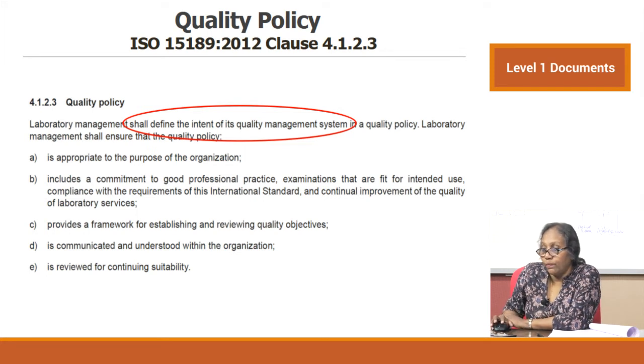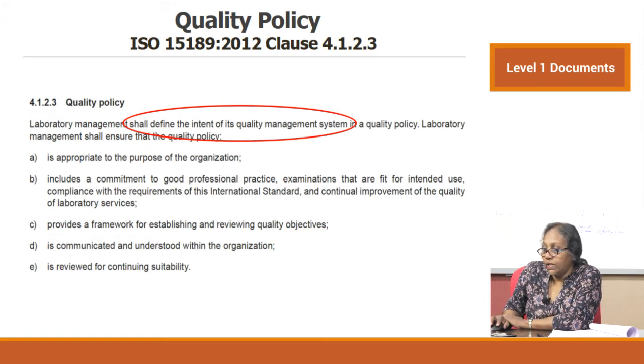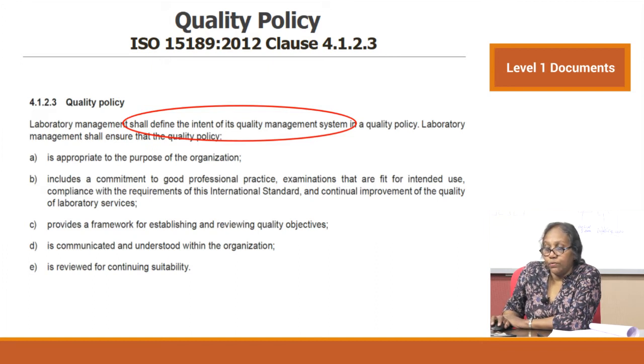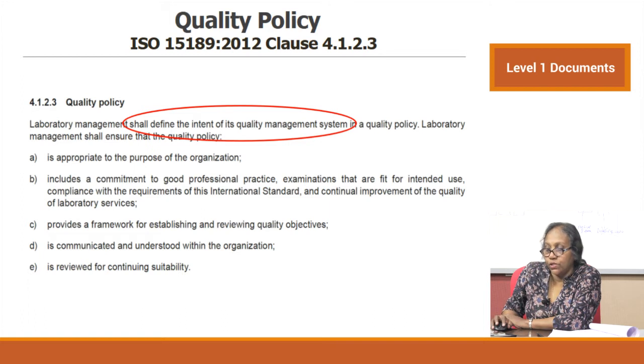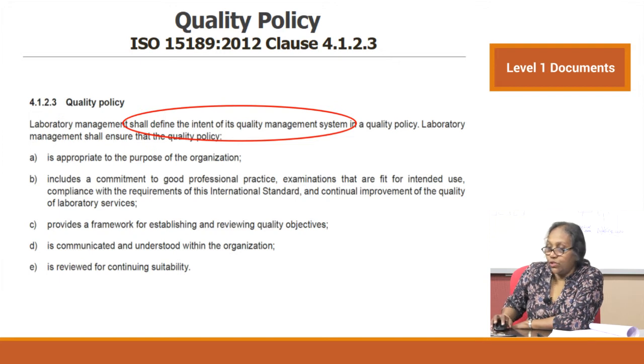The five conditions are: it is appropriate for the function and purpose of the organization; it includes a commitment to good professional practice, examinations fit for intended use, compliance with the requirements of this international standard, and continual improvement of laboratory services; it provides a framework for establishing and reviewing quality objectives; it is communicated and understood within the organization; and it is reviewed for continuing suitability.